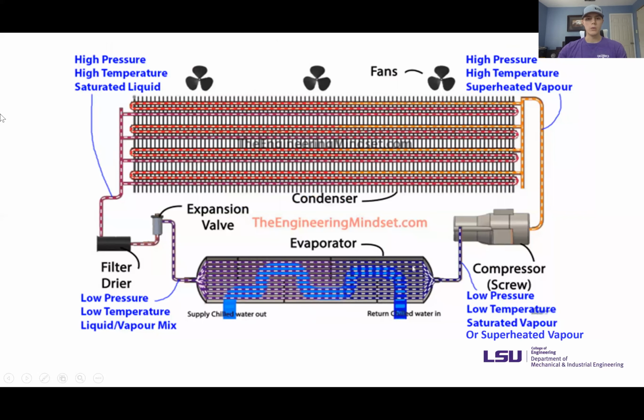So now that we know all of the main components, we can look at how that diagram would look with everything put together, starting from your compressor at low pressure, low temperature, saturated vapor, or superheated vapor, depending on the type of compressor being used. It flows to the condenser, where heat is removed from the refrigerant, and then exits at high pressure, high temperature, saturated liquid.